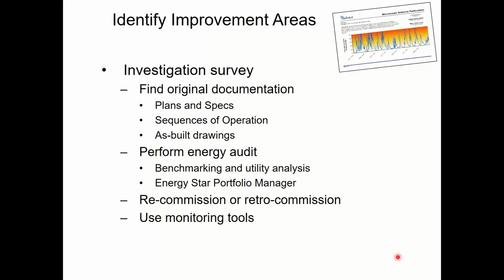And you can also do some monitoring tools. It could be stuff where you're using tools to just measure something once, right? Just to kind of see where you're at. Or it could be stuff that's continuously monitoring. For example, on HVAC, I may want to go get some static pressure readings on all my air handlers. I could do that continuously. I can install a manometer or a magnehelic gauge or a digital pressure sensor and have it track pressure continuously.